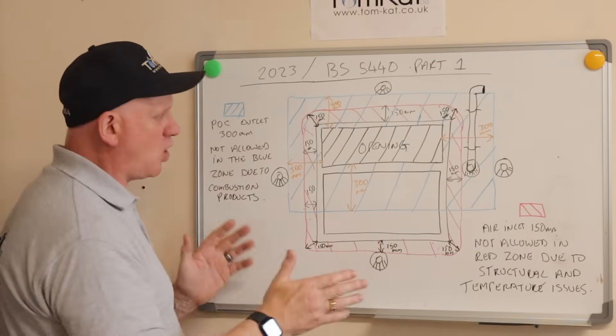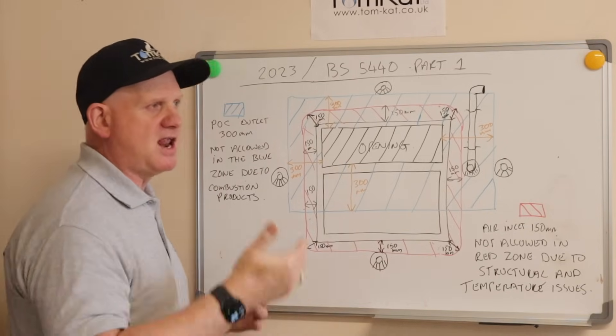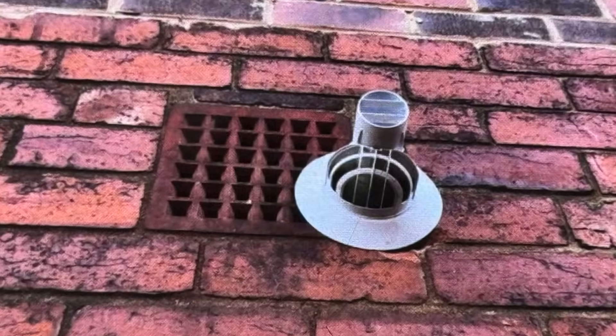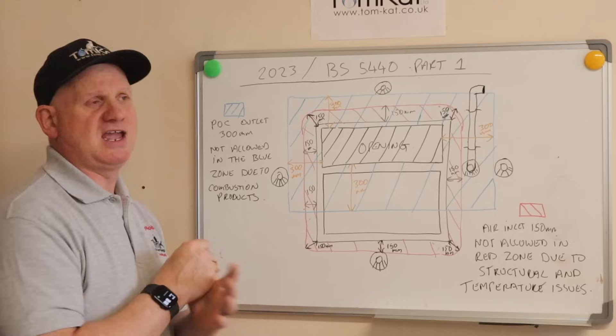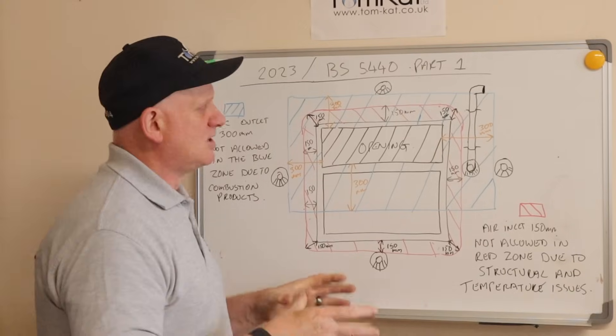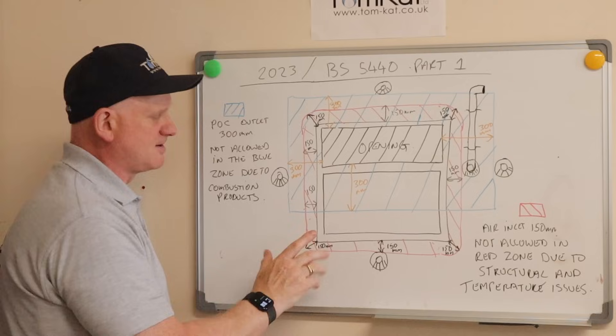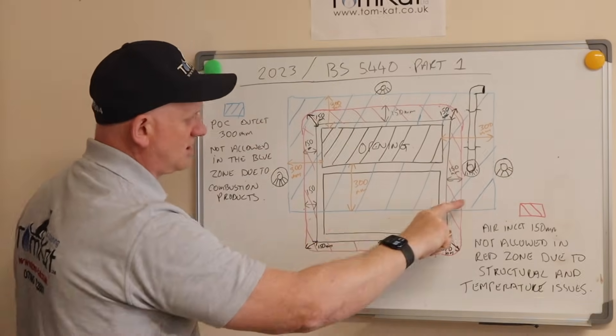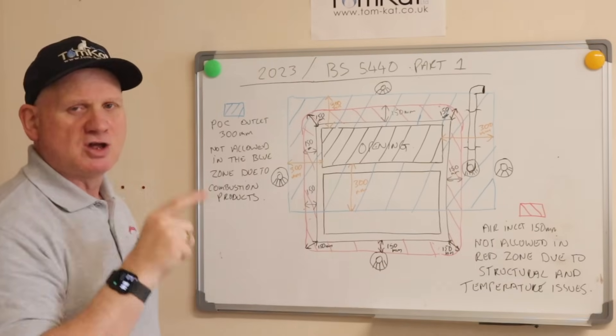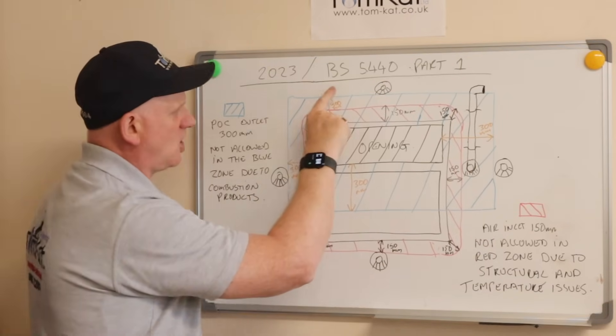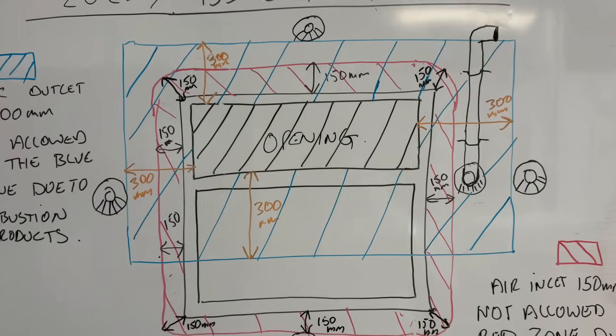Now when you're installing a fan flued boiler, which basically condensing boilers are, you have to be more than 300mm away from an opening in a building. So that could be a ventilation opening, it could be a window, it could be a door, it could be a patio door, it could be vented eaves. So you can see the blue section is 300mm away from this opening.